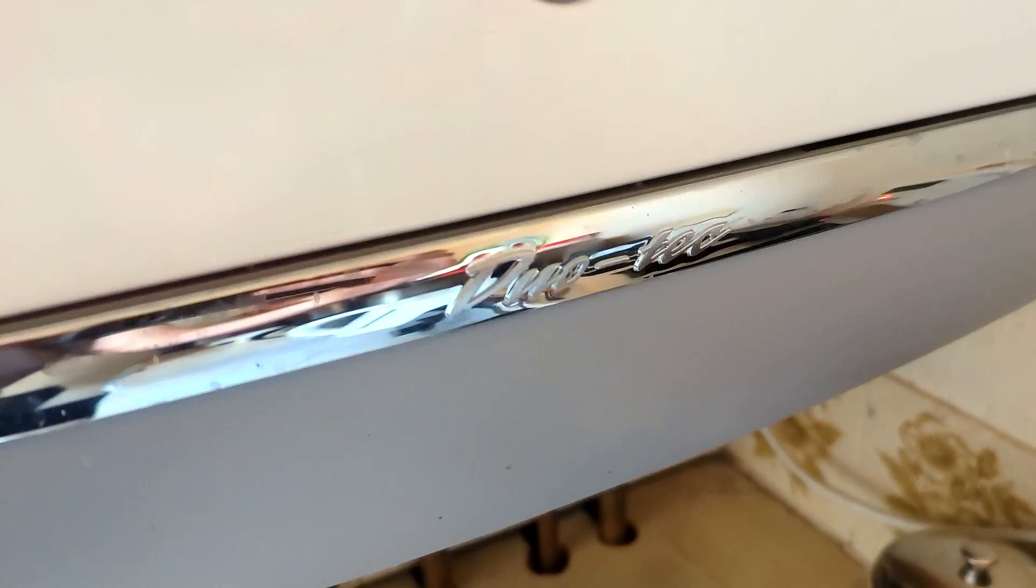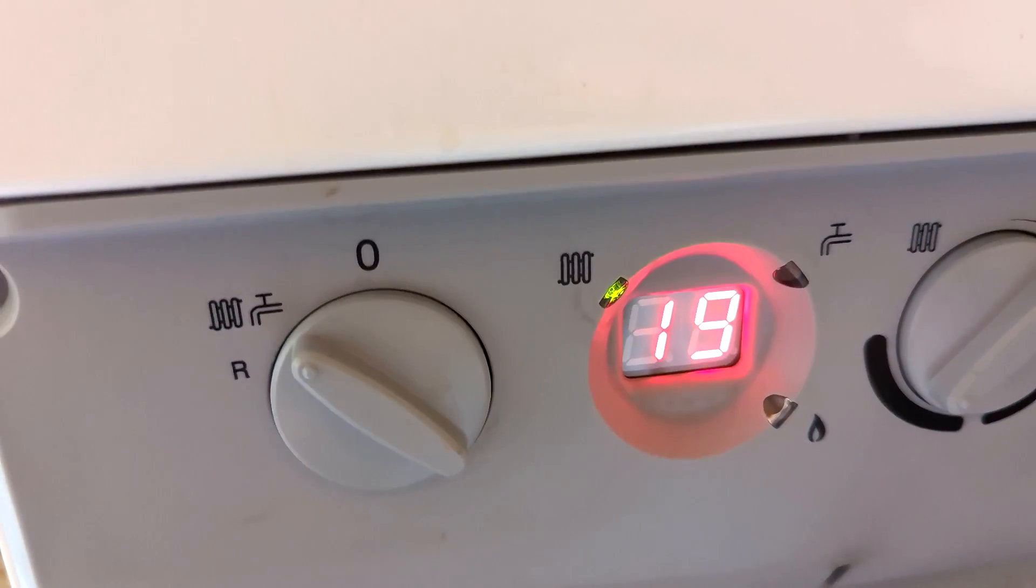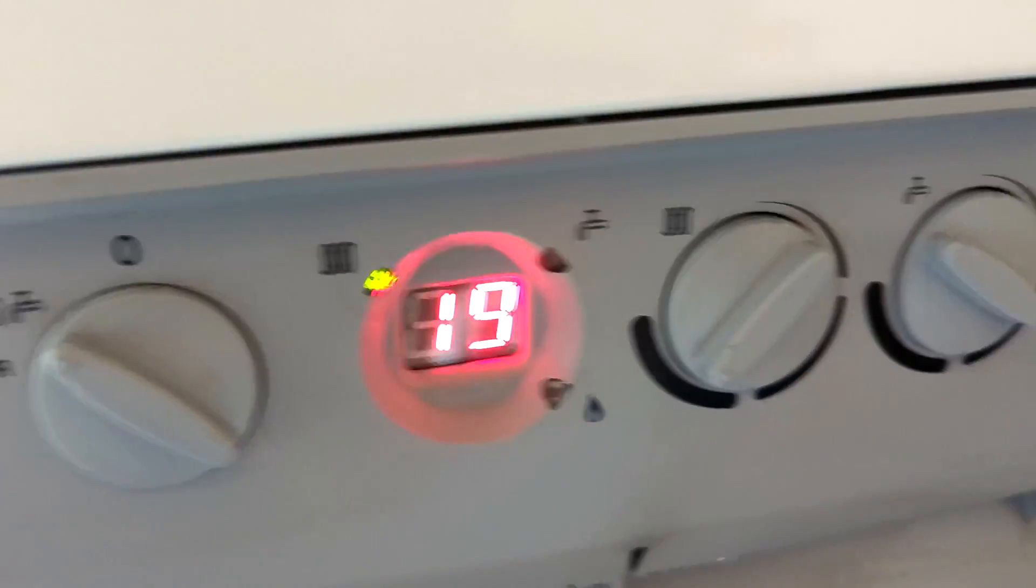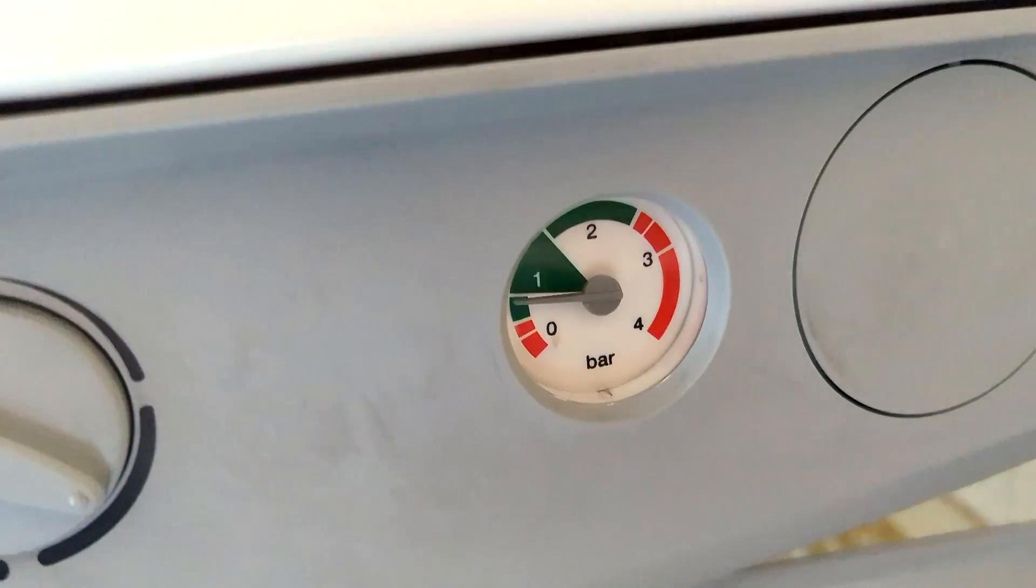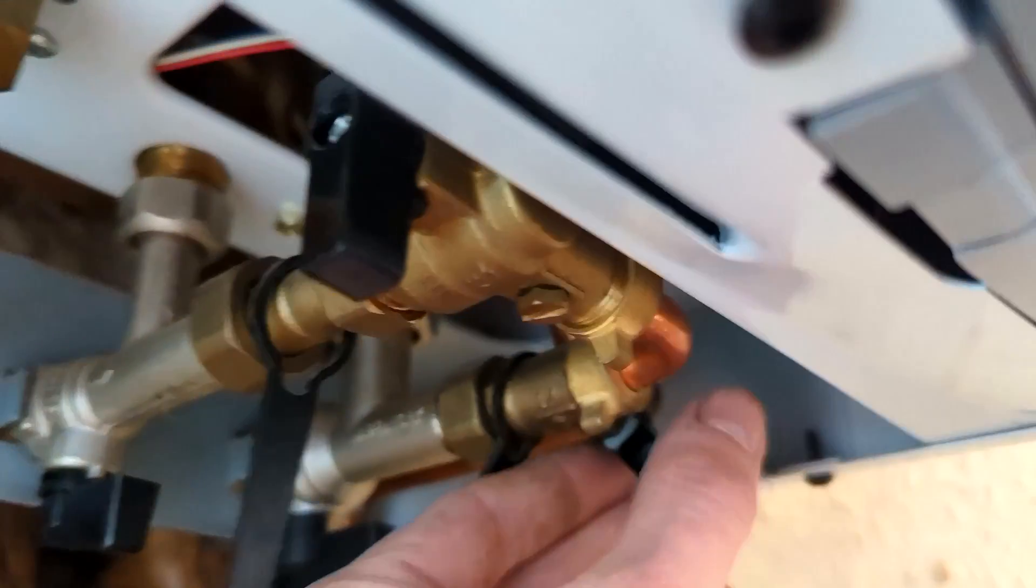So we've got a Baxi Duotec boiler, it is flashing E119 which is low water pressure, so we're going to top it off. We come underneath the boiler here. This one has got the filling loop that's meant to be vertical.